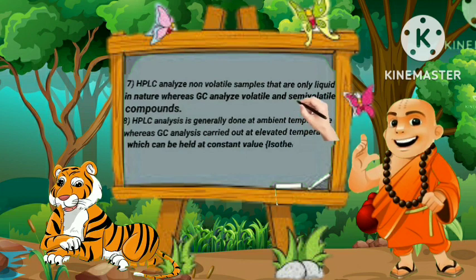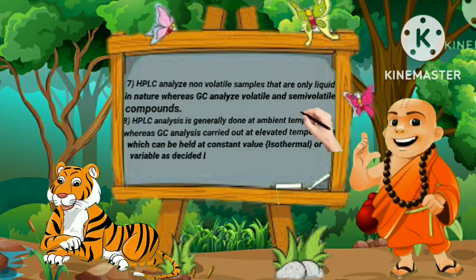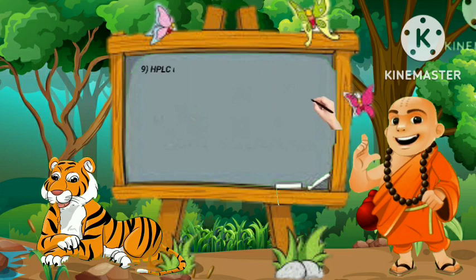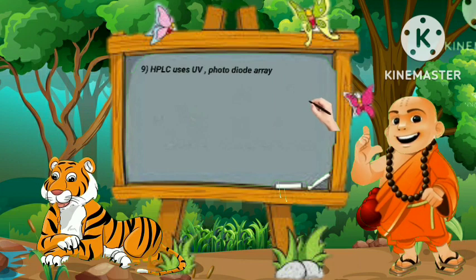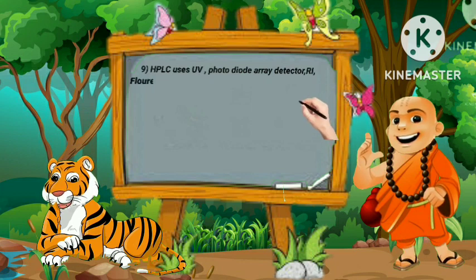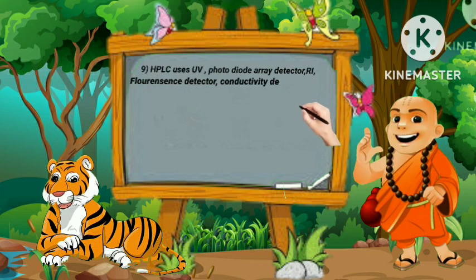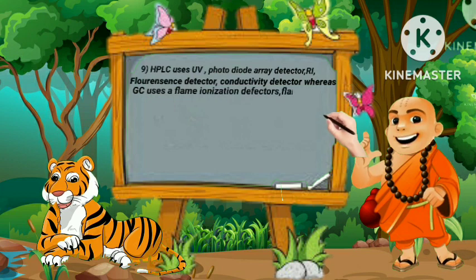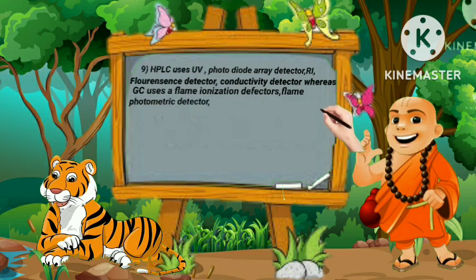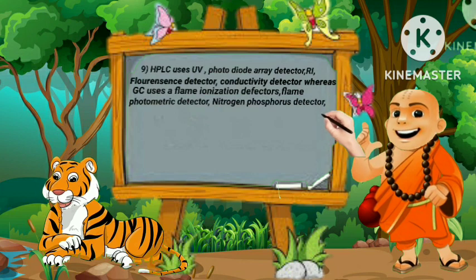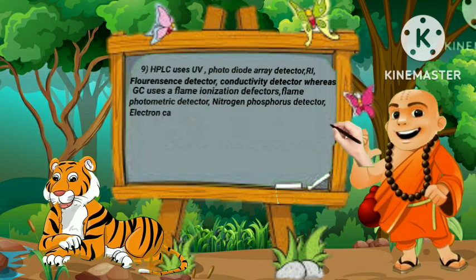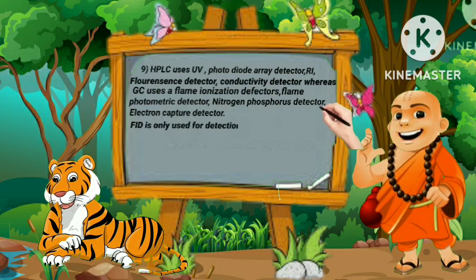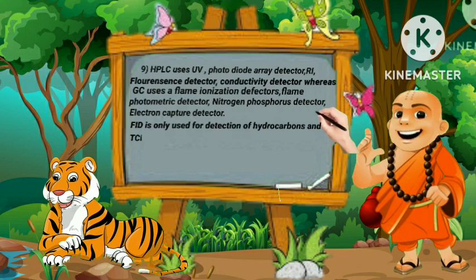Ninth, HPLC uses ultraviolet detectors, photodiode array detectors, refractive index detectors, fluorescence detectors, and conductivity detectors. Whereas GC uses flame ionization detectors, flame photometric detectors, nitrogen-phosphorus detectors, and electron capture detectors. FID is only used for detection of hydrocarbons, and TCD is universal and detects any substance.